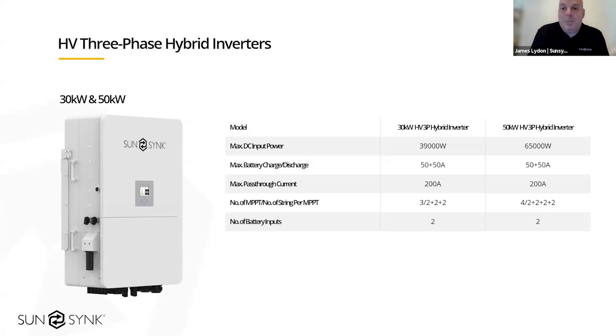On the 50, we can parallel 10 50s together, so we can have 10 50s connected together, given a max PV input of 650 kilowatt, and each 50 kilowatt high voltage hybrid inverter can have 2 of our high voltage battery stacks connected, and each stack is 61.4 kWh. So there's max potential storage wise of over 1.2 meg. So it just gives you an idea on the scalability of all the systems.